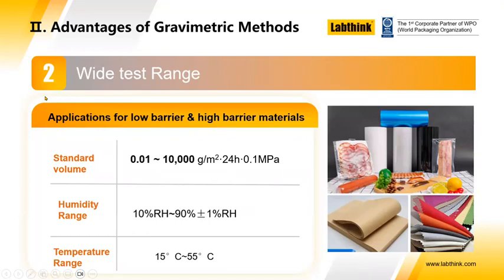So sometimes there's a misconception about E96 that it's only suitable for very permeable materials, like paper and board, or things like spun polyolefins or materials used for house wrap and suchlike, which are designed to be waterproof but breathable. Well, advances in the technology and the accuracy of balances, and the availability of sophisticated software to analyze results, have made this a method now, with our automated equipment, where we can confidently say that its applications are okay for a wide range of materials with transmission rates from as little as 0.01 up to 10,000 grams per meter squared per 24 hours per atmosphere.